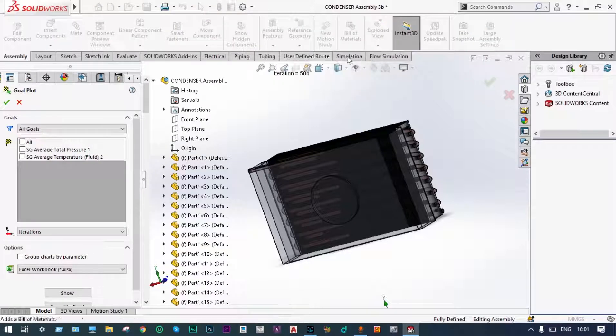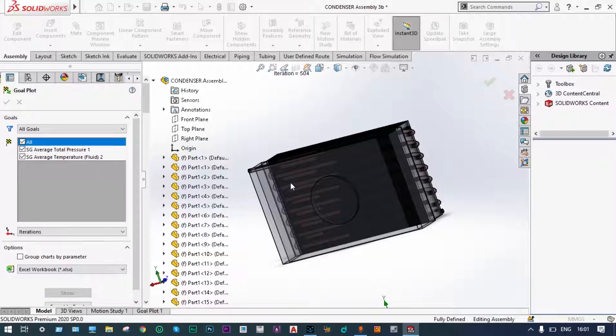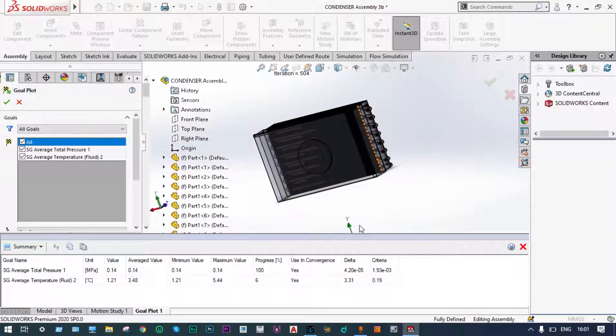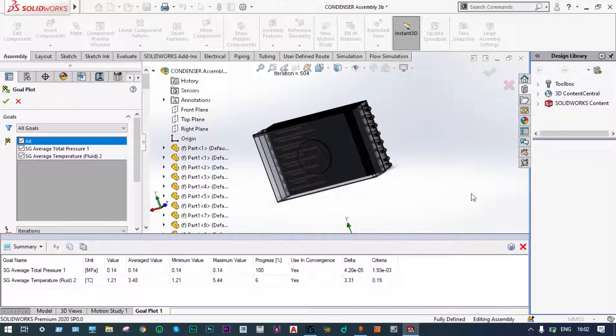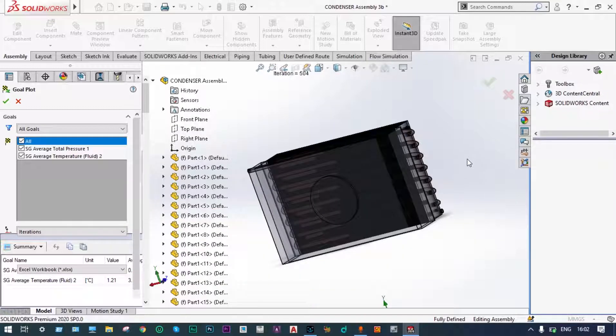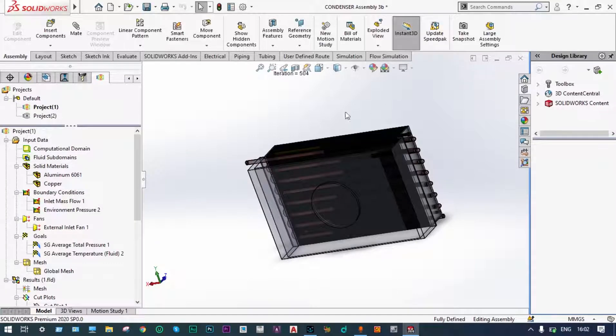Finally, we view the goal plots. We insert the two goals — average total pressure and average temperature at the exit location — and select all to show. After 504 iterations, the average total pressure is 0.14 megapascal and average temperature is 3.48 degrees centigrade, with a minimum of 1.21 and maximum of 5.44. The average temperature at the exit location of the evaporator is 3.48 degrees centigrade.